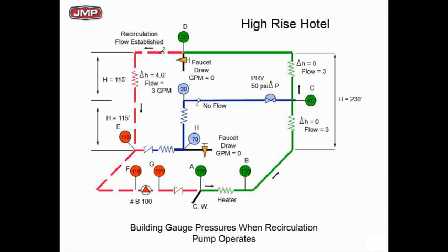So then on the 10th floor, we kept on going up to the 20th floor, at which time we had a down feed again, and we downfed all the pressures there from 20 back down to 70. So that pressure reducing valve, I hope you recognize on the 10th floor is the problem. Let's see how it's the problem.